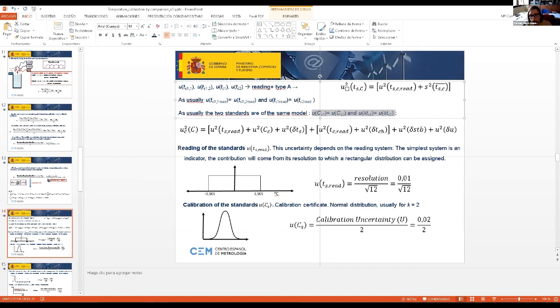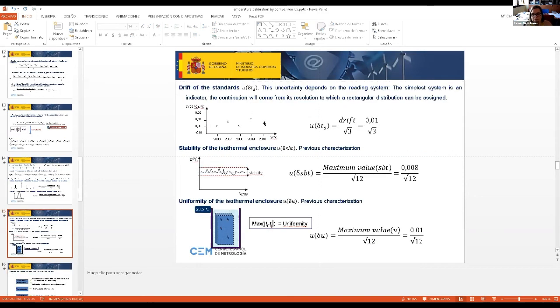Calibration of the standards. We go to the calibration certificates that usually give us the calibration uncertainty in normal distribution and for a coverage factor of 2. Drift of the standards. We go to the history of the thermometer, and usually the uncertainty component due to this drift is evaluated in this way, as a maximum variation, rectangular distribution, but we will consider as an interval the maximum variation, okay? Stability of the isothermal enclosure. We can take these uncertainty components from the previous characterization as the maximum value of the stability with rectangular distribution, and the same for the uniformity of the thermal enclosure.